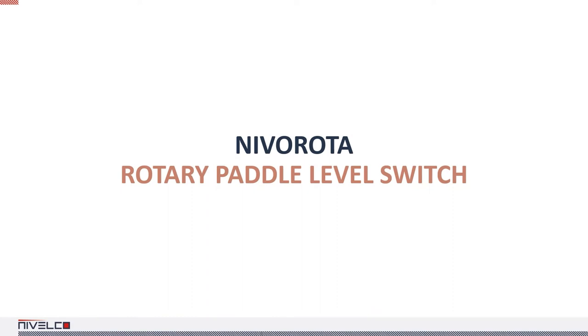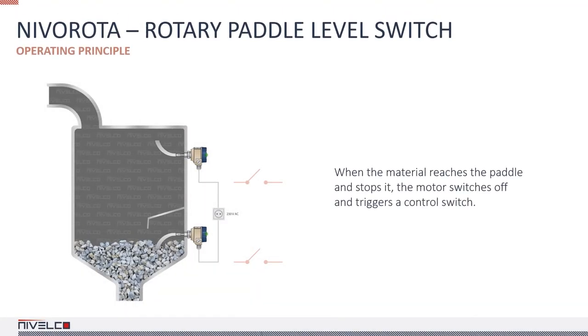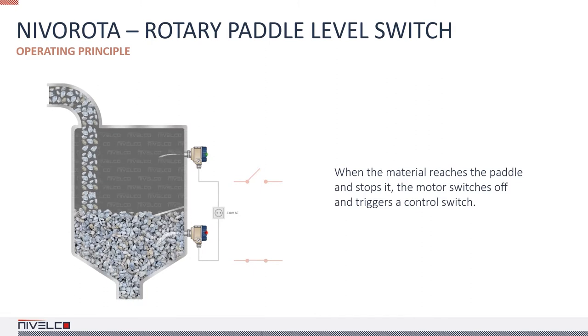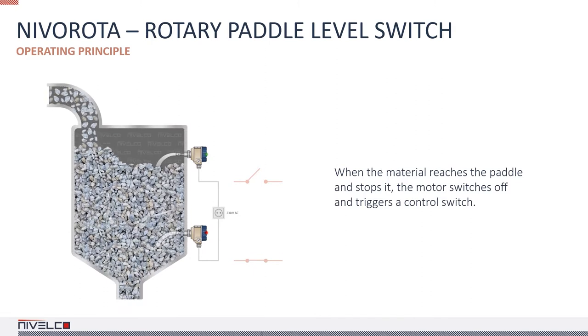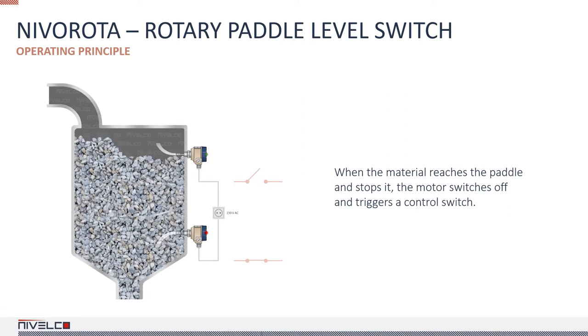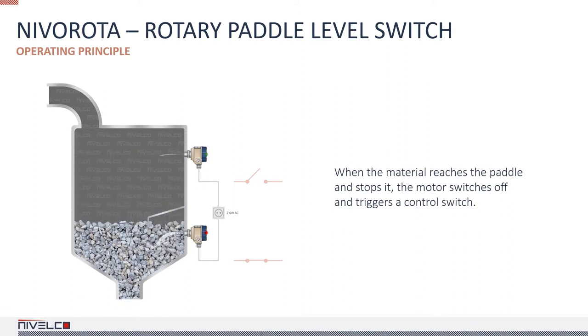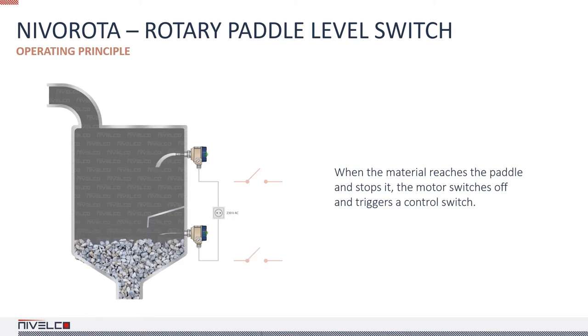Nivorota rotary paddle level switches detect the level of lumpy substances, powders, grains, and granules. A small electric motor drives the paddle, which rotates freely in the absence of the measured material. When the material reaches the paddle, the motor is switched off and the output switch is triggered. When the material level drops, the paddle is free to spin again, the motor is reactivated, and the switch returns to its original state.